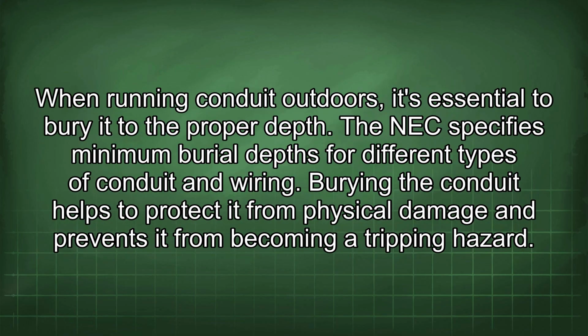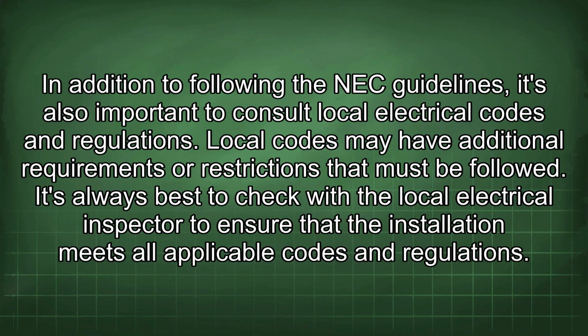When running conduit outdoors, it's essential to bury it to the proper depth. The NEC specifies minimum burial depths for different types of conduit and wiring. Burying the conduit helps to protect it from physical damage and prevents it from becoming a tripping hazard. In addition to following the NEC guidelines, it's also important to consult local electrical codes and regulations. Local codes may have additional requirements or restrictions that must be followed. It's always best to check with the local electrical inspector to ensure that the installation meets all applicable codes and regulations.